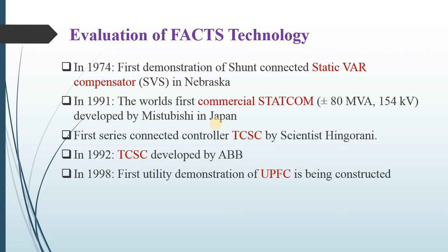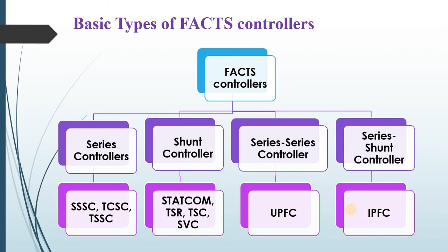FACTS controllers are mostly divided into 4 types: series controllers, shunt controllers, combined series-series controllers, and combined series-shunt controllers. The series controller FACTS devices are SSSC, that means static synchronous series compensator, TCSC, that is thyristor controlled series capacitor, and TSSC, thyristor switched series capacitor. These are the series controllers. Now STATCOM, that means static synchronous compensator, TCR, thyristor controlled reactor, TSC, thyristor switched capacitor, and SVC, static var compensator. These are the shunt controllers. In case of series-shunt controllers, there is the UPFC, that is Unified Power Flow Controller, and in case of series-series controllers, there is the IPFC, that is Interline Power Flow Controller.